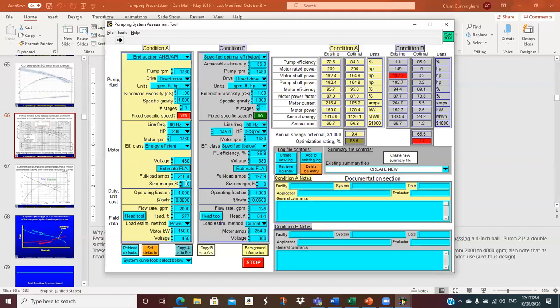Okay, and then we get down to the field data. So we've got 2,000 GPM. We strapped the ultrasonic flow meter on there, and we actually measured 2,000 GPM. It's best if you can actually have a good flow meter and measure it. You've got to do the best you can. Head, that's the total pump head. Right now it's sitting on 277 feet. And we need a power measurement of some sort.